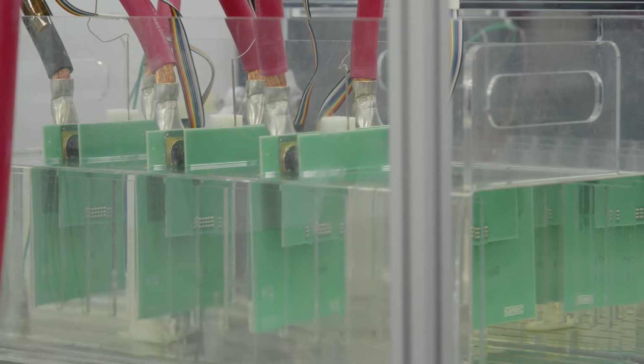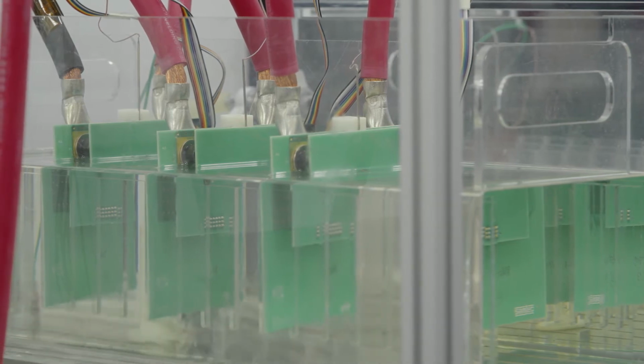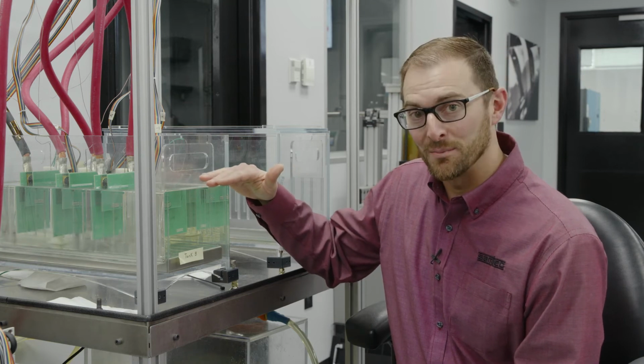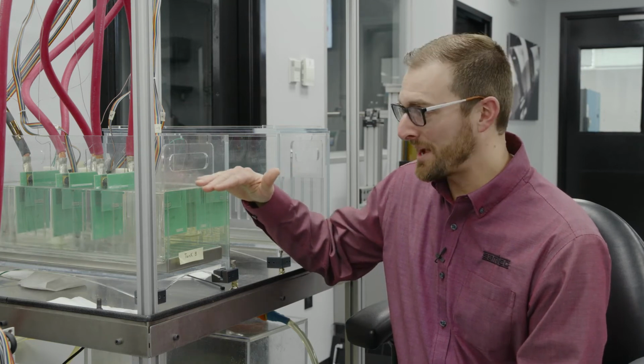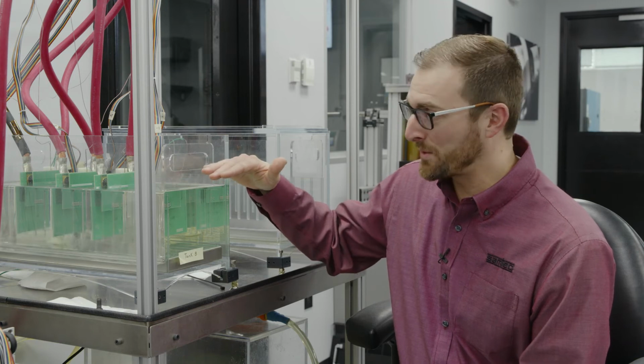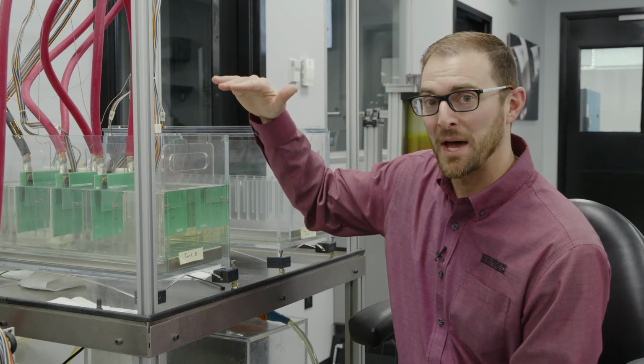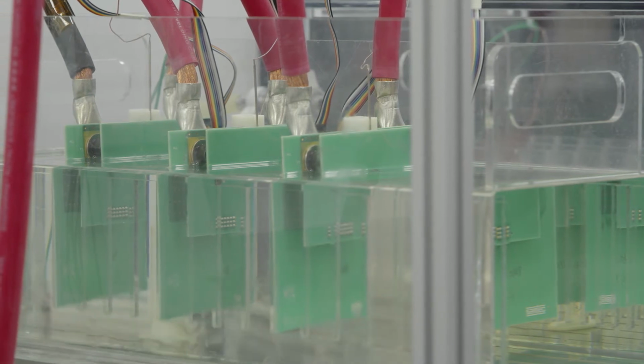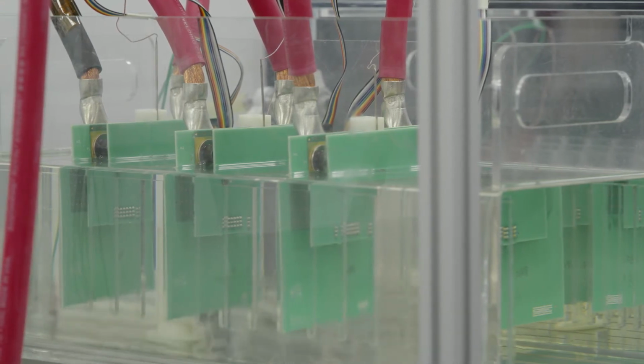We're here in the lab at Samtec where we're doing our immersion cooling test. Here, the connectors are below the liquid level and we have that controlled, and then the power is coming in through the top. We cycle the current through the test and evaluate the temperature change as it goes.